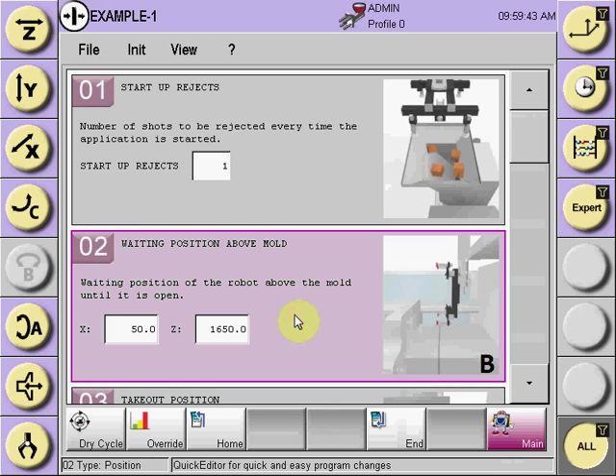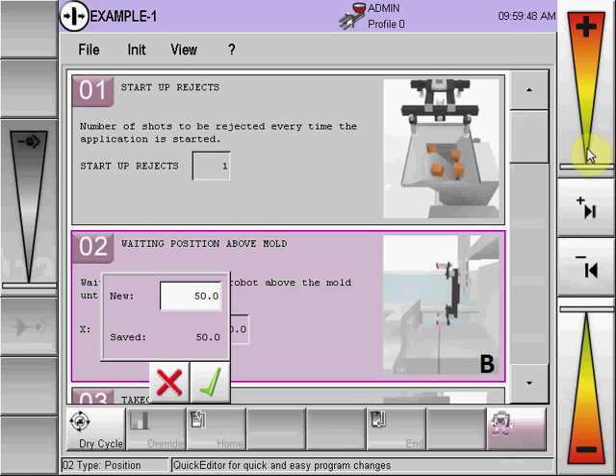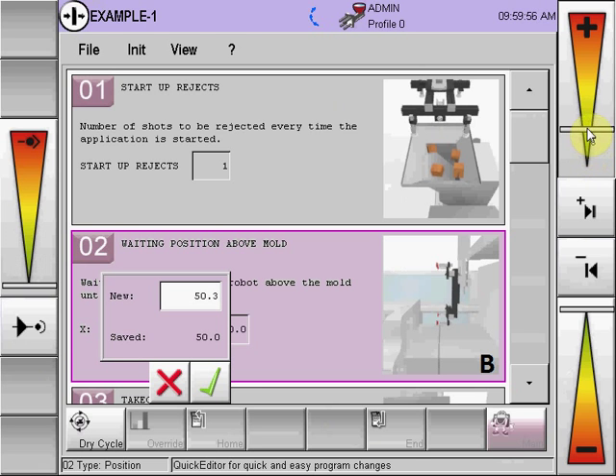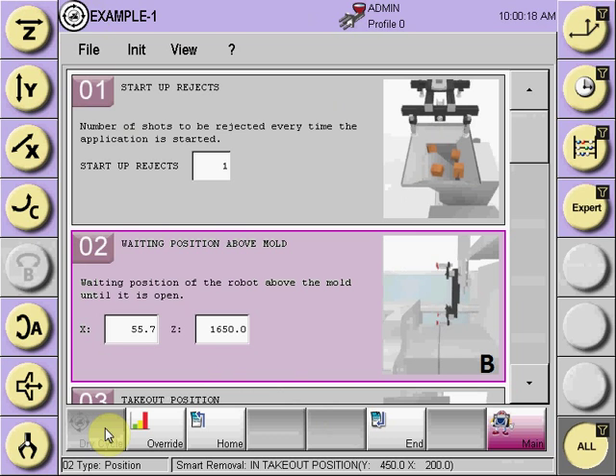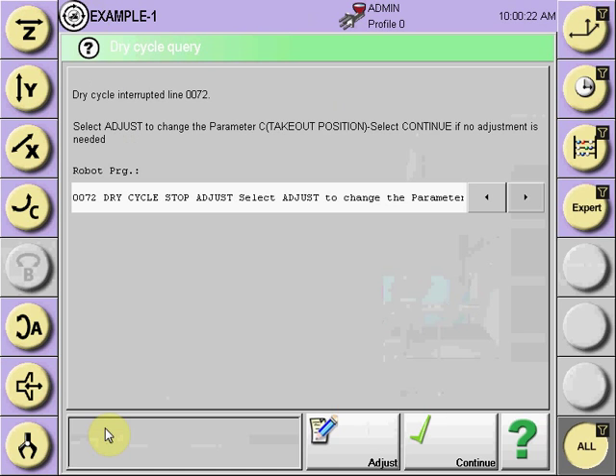To adjust, the graphic image shows the associated letter — waiting above mold B. Select that box, then select the axis that needs adjustment. This allows you to adjust plus or minus 10mm each adjustment. Move it to the position required for the adjustment. If no adjustment is needed, select continue.